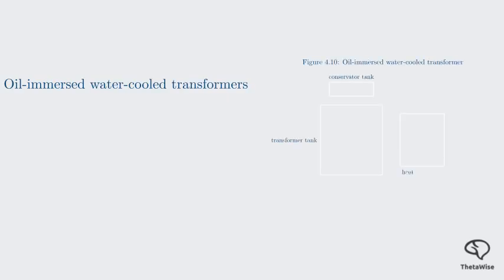Finally, for the very largest transformers, oil-immersed air cooling is not enough. They require an even more active and powerful cooling system. This is the oil-immersed water-cooled transformer. Let's trace the heat flow in this system using Figure 4.10. Here, the heated transformer oil is not cooled by air, but by water.